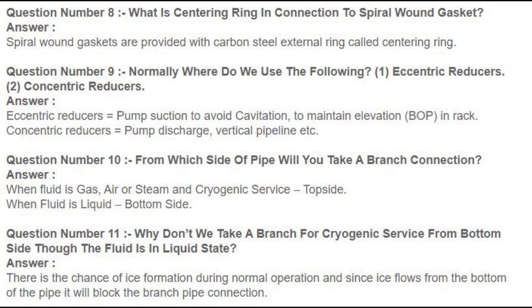Question number 9: Normally where do we use eccentric reducers and concentric reducers? Answer: Eccentric reducers are used at pump suction to avoid cavitation, to maintain elevation (BOP) in rack. Concentric reducers are used at pump discharge, vertical pipelines, etc.